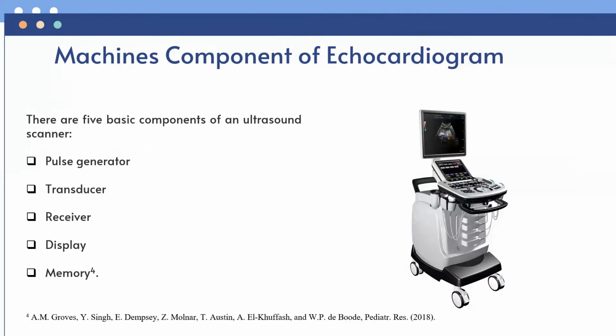There are 5 basic components of an ultrasound scanner. The first is pulse generation, which applies high amplitude voltage to energize the crystal. Then the transducer, to convert electrical energy to mechanical energy and vice versa. The third is the receiver, to detect and amplify weak signals. And then the display, to display ultrasound signals in a variety of modes. And the last is memory, to store the video display.